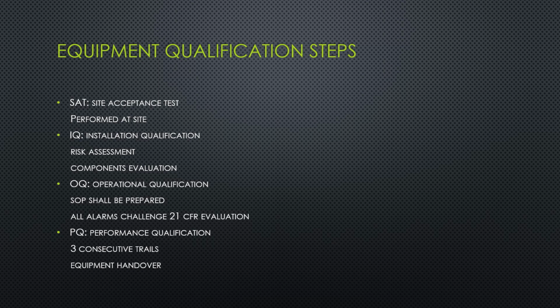Next is installation qualification, so IQ. During the installation qualification, we go with the types of the risk assessment and components evaluation. So here, whether the equipment is being installed properly, what types of risks have occurred during the installation, and all the components that have been associated with the equipment will be evaluated. All the spares, all the parts, all the requirements to run the equipment or the instrument will be checked during the installation qualification.